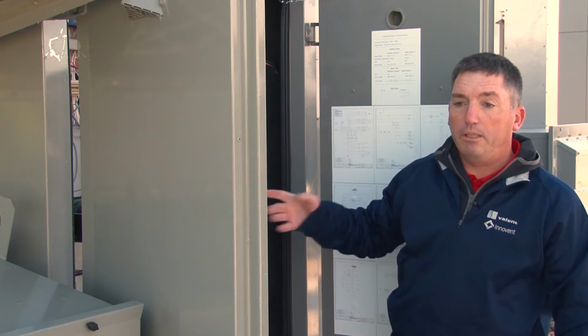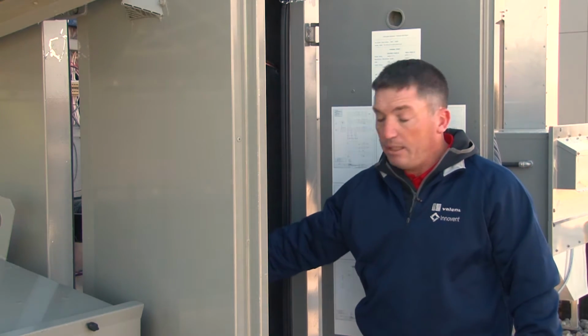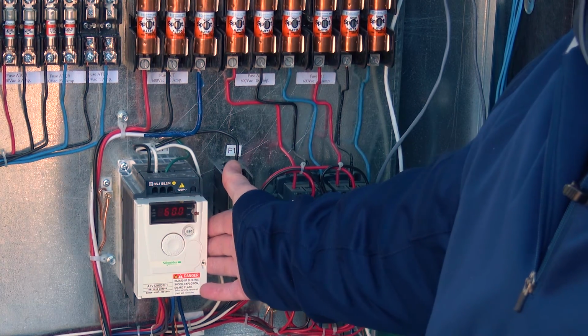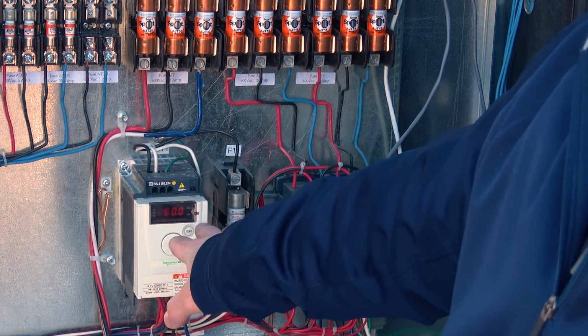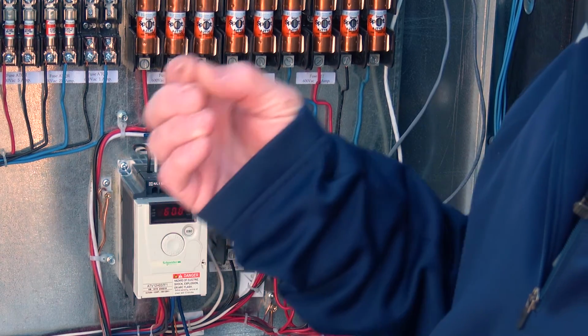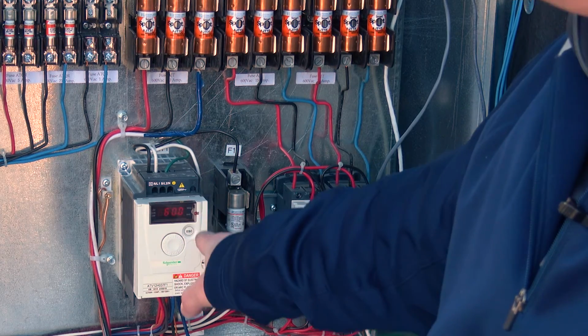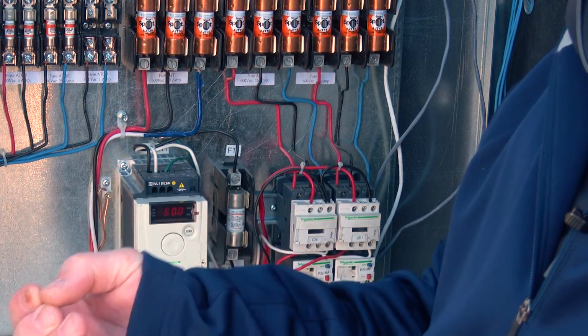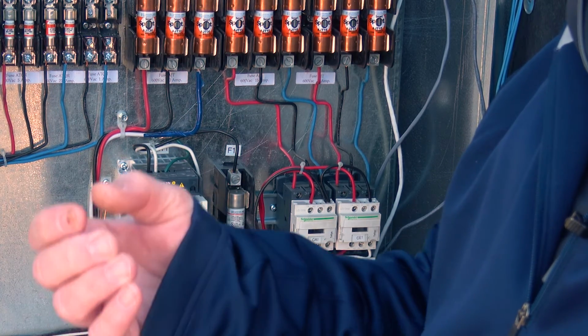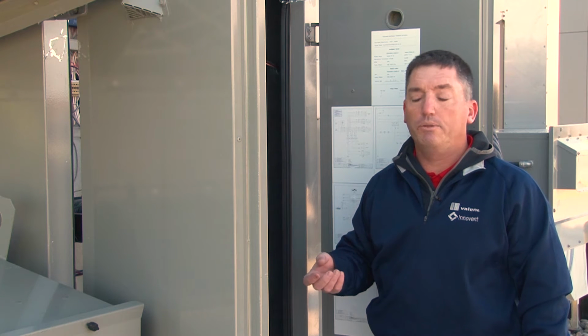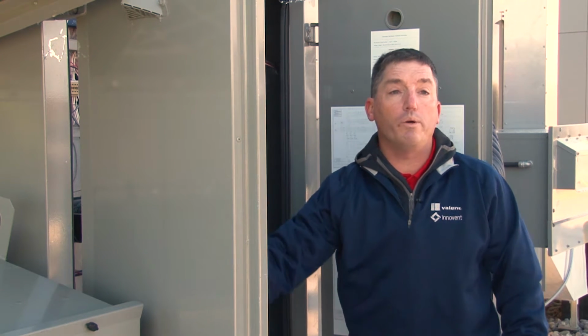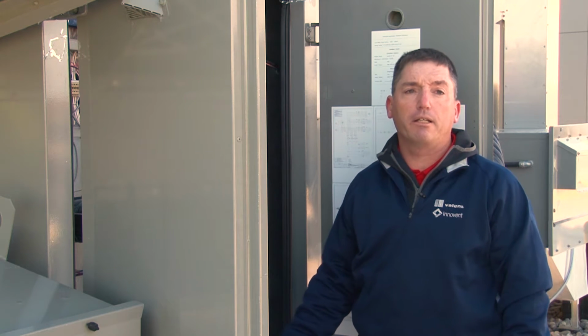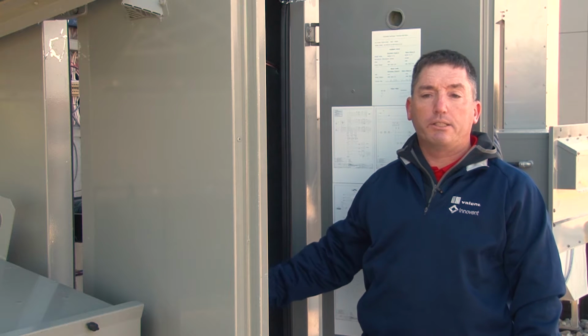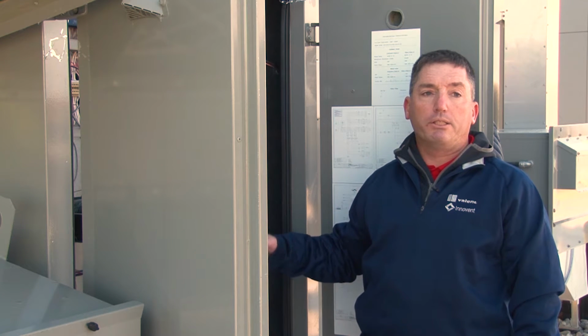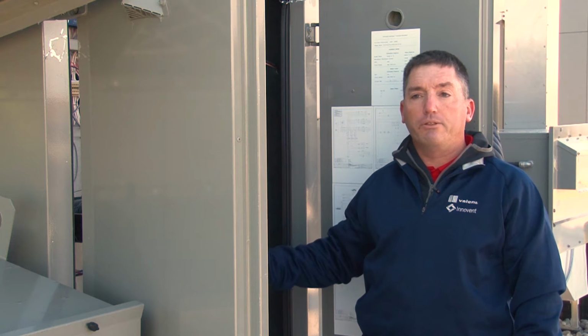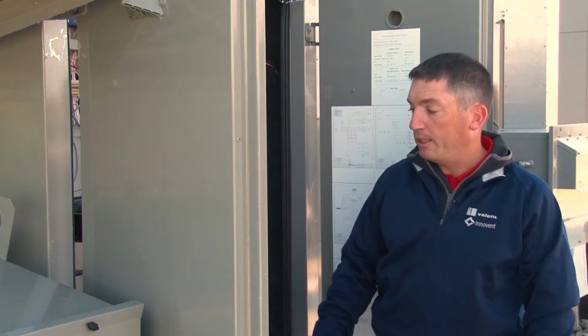The energy wheel, as I mentioned before, it rotates. It is controlled by this variable frequency drive here. Again, during normal operation, that drive is just going to show the operating frequency. If there is a fault on the drive, it's going to flash a 3-letter code, and then you have to refer back to the drive manual to see what that code relates to. The most common code would be OLF, which is an indication that the motor has exceeded the rated amperage. In most cases, just cycling the power to the unit is going to reset the drive, and it's going to resume operation again.